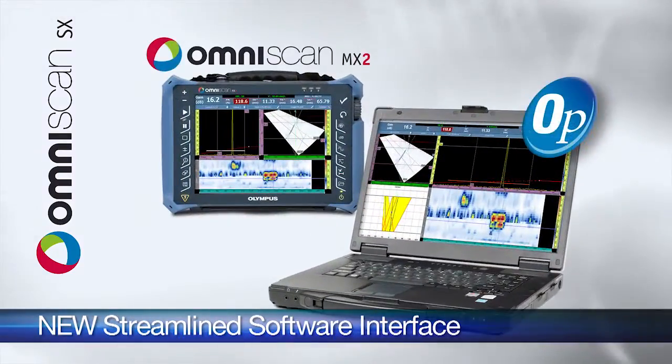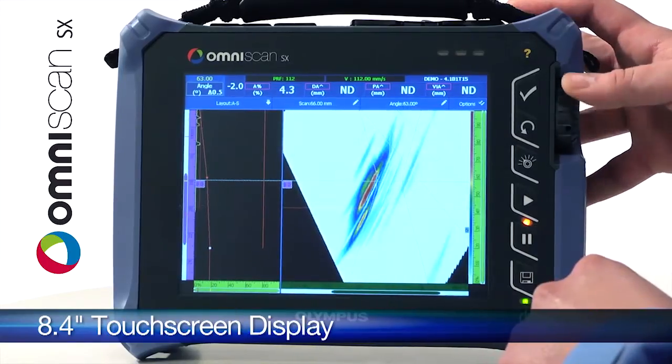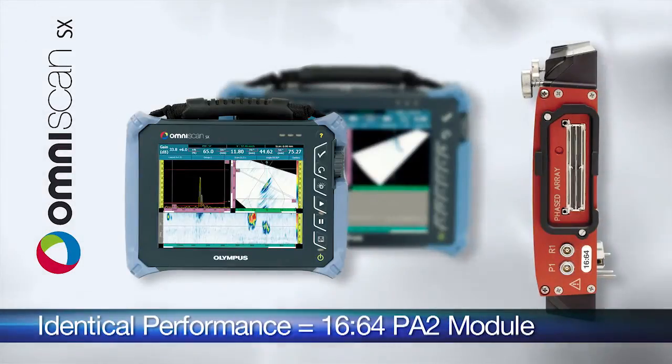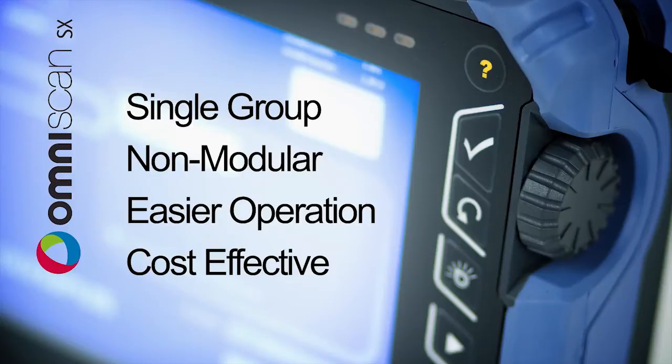which will also be available on the OmniScan MX2 and OmniPC software, the OmniScan SX incorporates an 8.4-inch touchscreen display as well as identical performance found in the latest 16:64 PA2 modules used with the OmniScan MX2. The OmniScan SX is a single-group non-modular instrument which is easier to operate and more cost effective for less demanding applications.